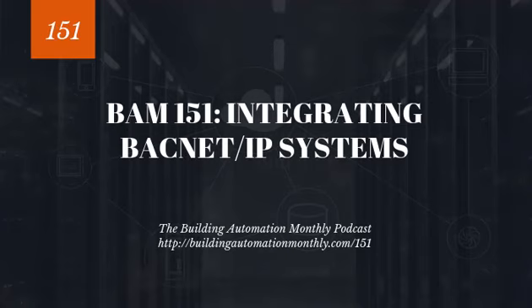So, protocol specifics for BACnet. What we have to remember is BACnet is primarily a broadcast protocol, meaning that it utilizes Who-Is, I-Am, Who-Has, I-Have for interrogating devices. And BACnet is primarily a device architecture, meaning you have a device, and under that device you have objects.